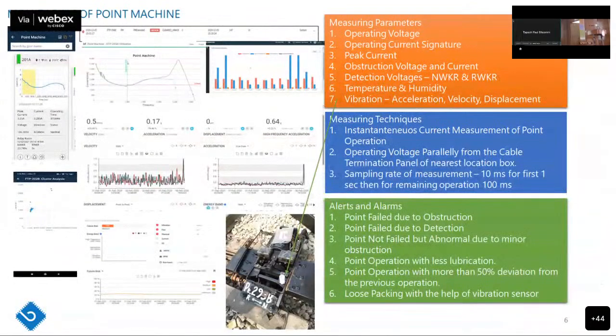In the point machine, we are monitoring operating voltage and operating current signature. The point is an event, not a continuous operation, so the biggest challenge is that it is an event-based system. Whenever required, the station master operates the machine, and at that time we don't know the health of the point machine — whether it will operate or not, we don't know initially. So monitoring this machine with event data is very important, because if I had a system with continuously flowing current or voltage, we could monitor it and predict failure based on time series data. But in the case of a point machine, this is event data, so we need to figure out how to capture this event data and identify if the machine is misbehaving or if there is an abnormality.